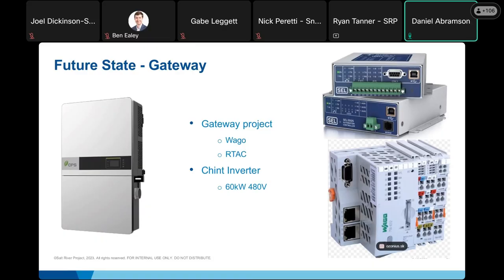Through programming and testing, we're using the standard as a baseline for how we model the points and modes. Functionally, it's an interpreter between our enterprise systems and the field device. We use DNP3 upstream to speak with the gateway from our DERMS, and then Modbus downstream to the inverter and its registers, because that's the protocol that Chint speaks.